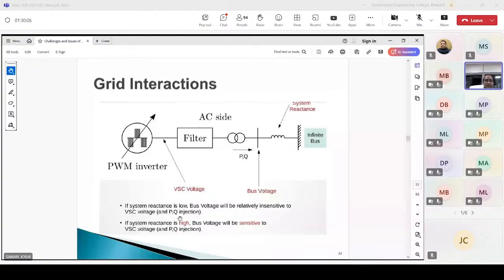Some important facts: if the system reactance X is low, the RE installation is connected to a strong system, and the bus voltage will be relatively insensitive to VSC voltage and P and Q injection. If you vary P and Q while X is low, the bus voltage is likely to be insensitive, so the variation in voltage is lesser. This holds whether you vary P alone, Q alone, or both simultaneously, the change in bus voltage will be lesser if X is low, and vice versa.